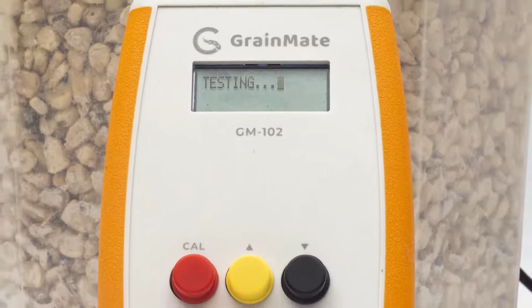Previously, you had to insert the probe in a sample and wait for up to 5 minutes to get a reading. Now, we have a better way of taking the readings. We now have a dedicated test button that you can use to initiate a test. We have developed an intelligent algorithm that has reduced the time it takes by more than 50%. The test now runs in the background and displays the final reading within a shorter time. And we've included a buzzer that will beep to tell you when the reading is ready.